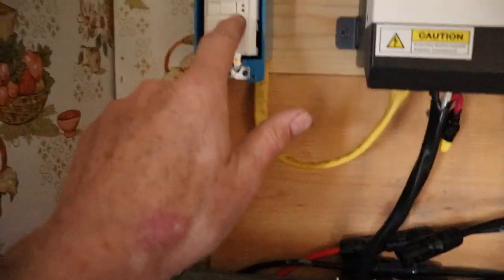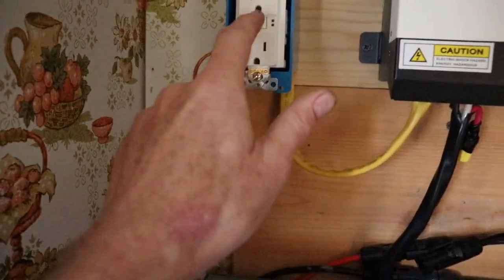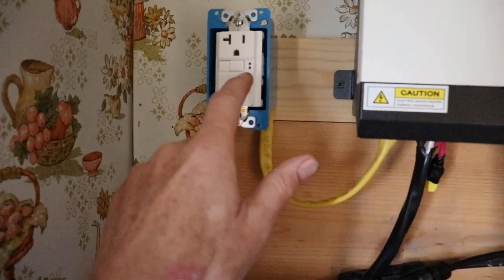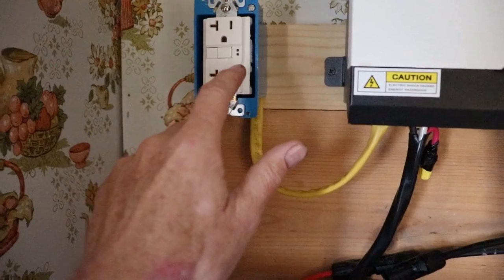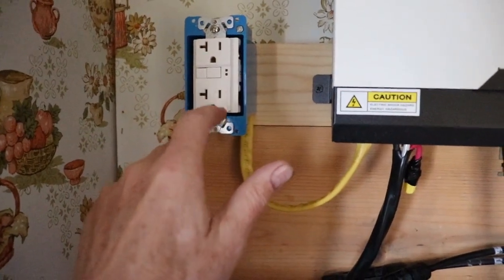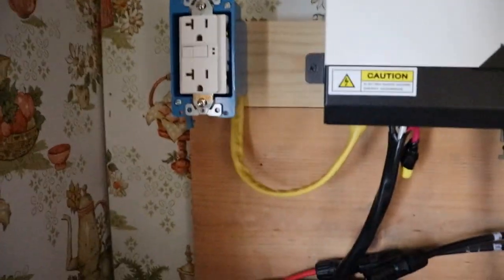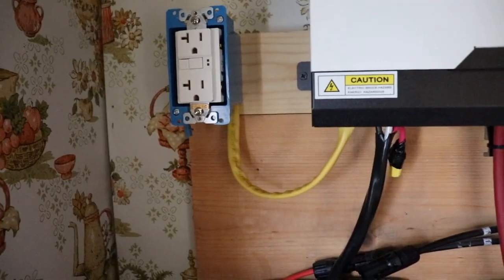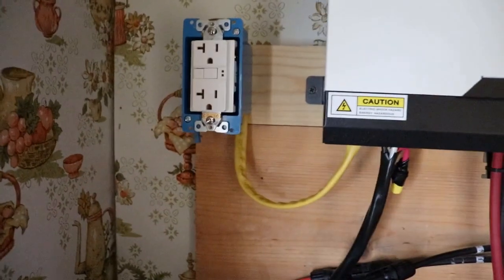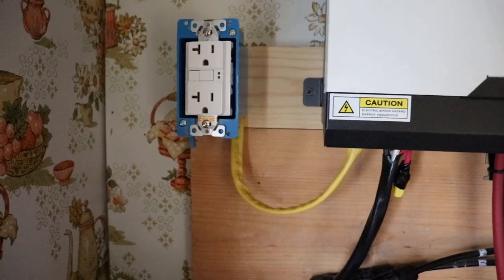This right here is a GFI switch, a 20 ampere. That's all I need for the input on this. My generator is only 15 amps at 120 volts on the output, so that's all it's going to get anyway. 20 is more than enough. It'll break the circuit if something goes wrong with the inverter on the generator.